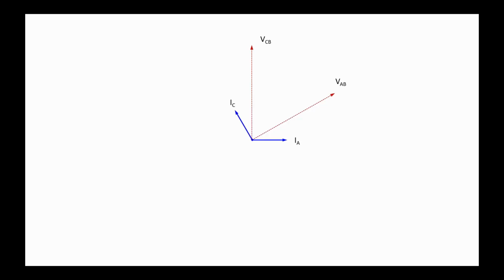But the VARs on a 2-element wattmeter, where the voltage and current are in phase with each other, are non-zero because you've got an inherent 30-degree phase shift, but they're in opposite directions. So the VARs on element 1 and the VARs on element 2 are equal in magnitude but opposite in direction. They cancel each other out, and I get 0 VARs because my voltage and current were in phase, but I get actual watts because I had current and voltage in phase.